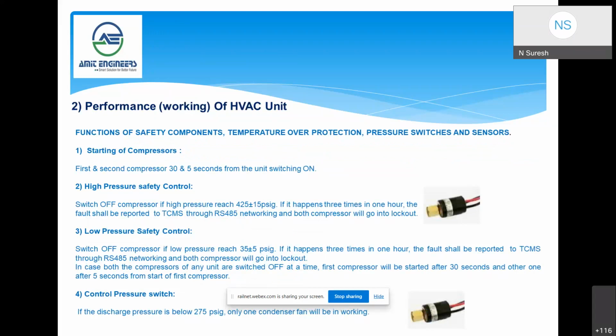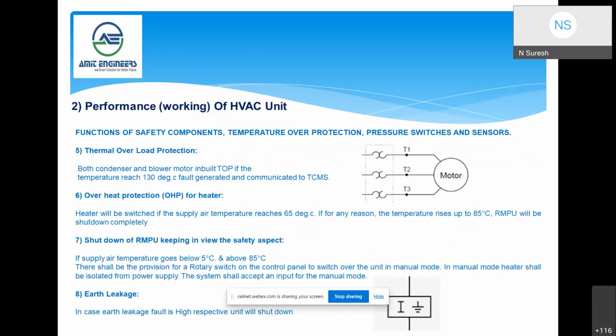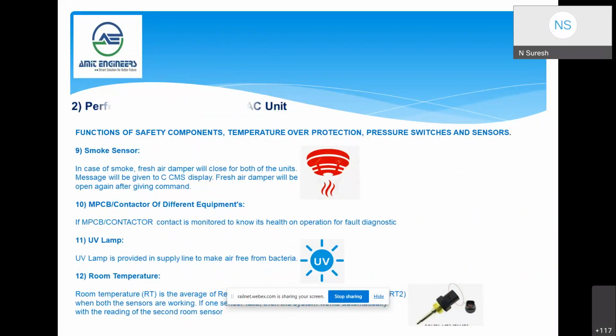These are all the safety components in the system. System level protection includes the high pressure switch, low pressure switch, and control switch. For component safety, the motor has an inbuilt TOP, and there is heater protection with three levels: 65, 85, and 130. A smoke detector for fresh air will indicate any external smoke, immediately shut down the fresh air damper, and give a signal to the TCMS for immediate action. The UV lamp is new, introduced in this project to give better air quality.